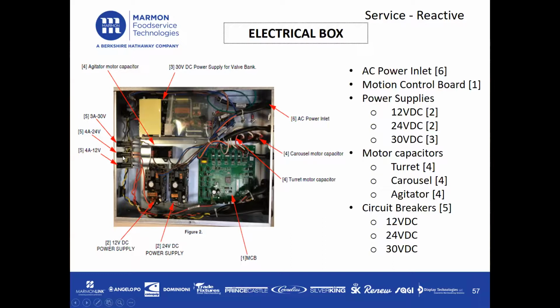We have our circuit breakers here that tie into our DC voltage power supply circuits. The one on top is 30 volts, 24 volts, and 12 volts DC. We also have our capacitors inside the electrical box. This big one right here is our agitator capacitor. Over here, the one on the left is our turret motor capacitor, and the one on the right is our carousel motor capacitor. This board that you see here is our motion control board for the unit.